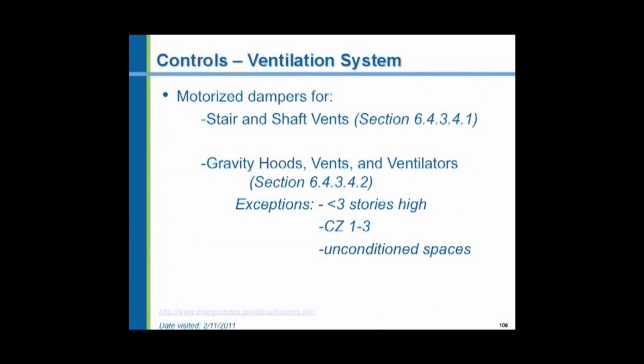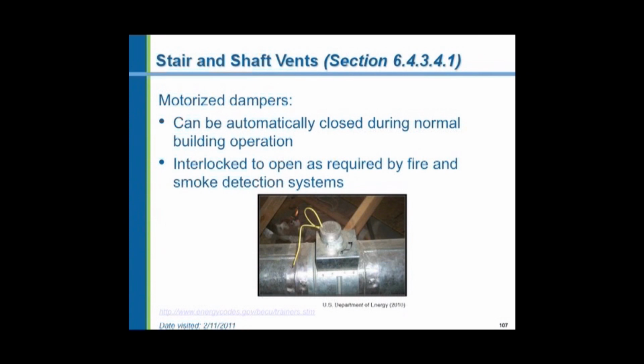On dampers for stair and shaft vents, they want dampers, motorized dampers, if the building is 3 stories or more high. Shorter buildings, 1 and 2 story buildings, stairwell vents, for instance, venting smoke from an exit stairwell at the top in the roof, they can have gravity dampers rather than powered dampers. The motorized dampers automatically close during normal building operation. These would be for the elevator shaft or the stairwell vents, and they would be opened as required by the fire and smoke detection systems. And sometimes there are even requirements for pressurizing the stairwell with outside air, with clean, fresh air, to keep the smoke away from the means of egress.